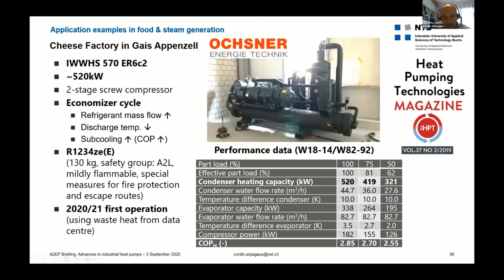Here are some performance data: water heating from 18 degrees up to 92 degrees, giving a temperature lift of 74 Kelvin, which is quite high. The COPs reached are in the area of 2.85 to 2.55, depending on the part load.